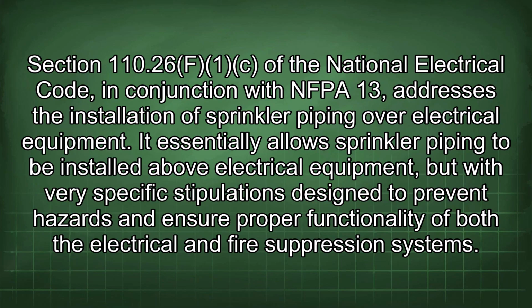Section 110.26(F)(1)(c) of the National Electrical Code, in conjunction with NFPA 13, addresses the installation of sprinkler piping over electrical equipment. It essentially allows sprinkler piping to be installed above electrical equipment, but with very specific stipulations designed to prevent hazards and ensure proper functionality of both the electrical and fire suppression systems.